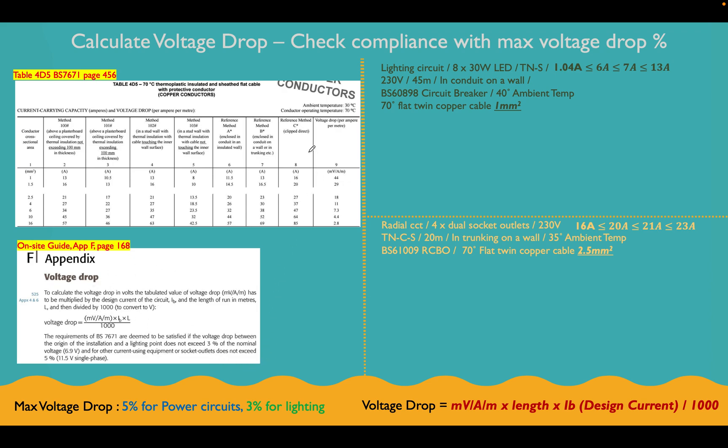Okay, so let's look at this first. Before, what we did, we went down this column here. We had reference method B, because we're in conduit or trunking, and we went down to 13 amps. We need our cable for the lighting circuit to be able to take 7 amps. So we went here and we went 13 amps is what we'll do. And we went across and selected our cable size, which was 1mm there.